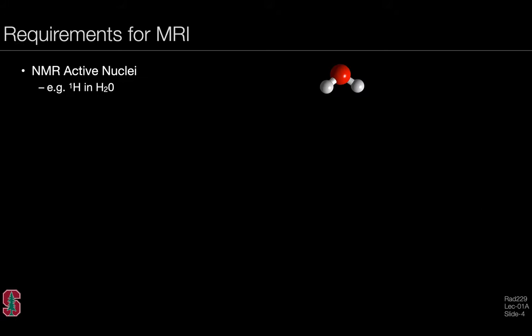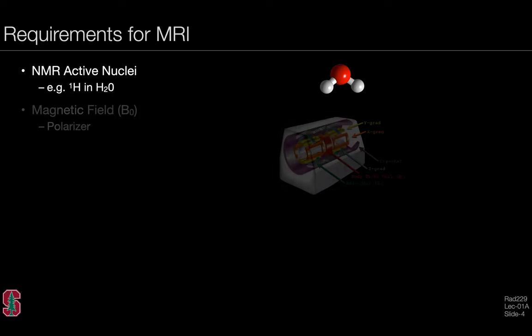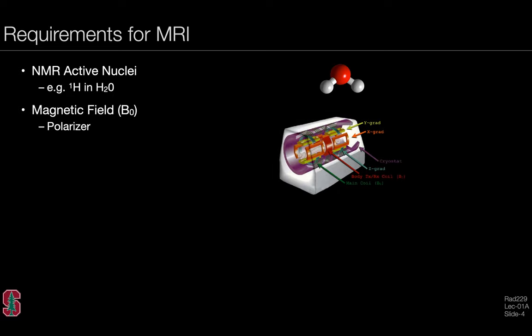We begin by describing the requirements for MRI. The first requirement is an NMR active nucleus, for example hydrogen in water. We also need the main magnetic or B0 field, which serves to polarize the spin system and make it available for detection. An RF system, or B1 exciter system, is also required to tip the magnetization away from its equilibrium position.